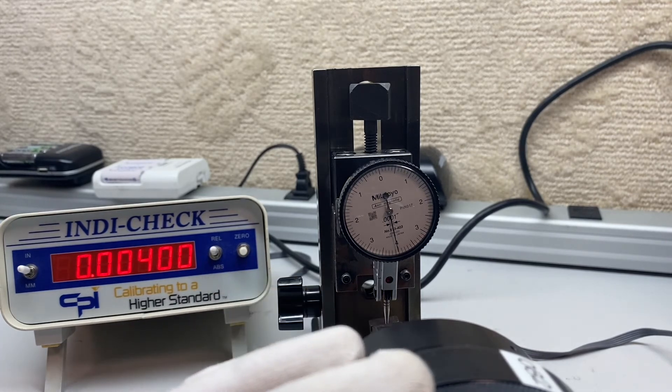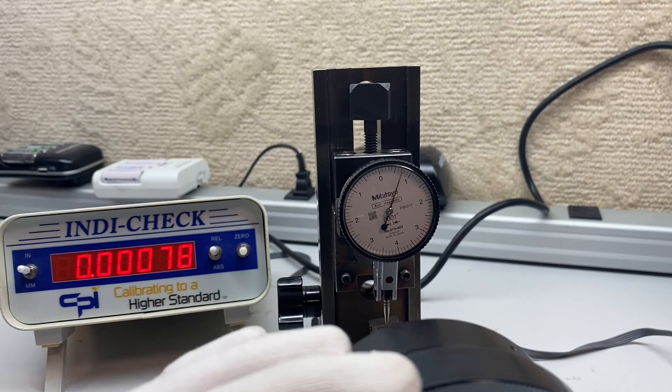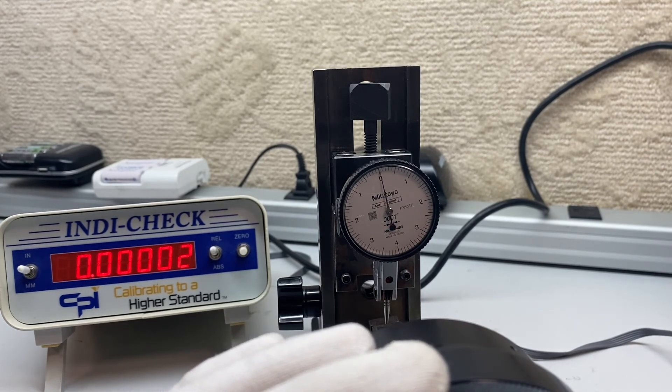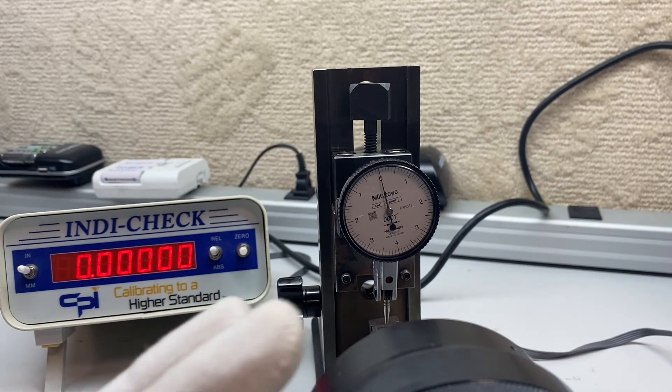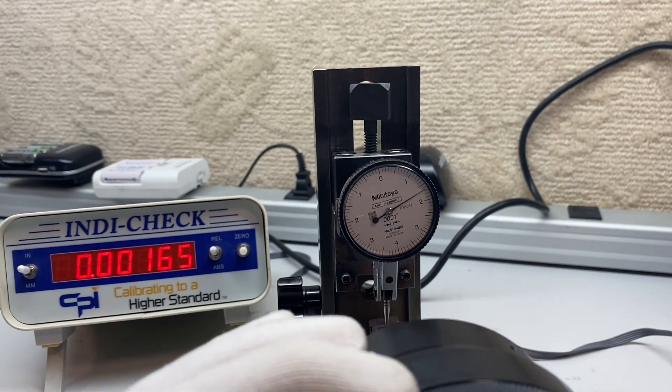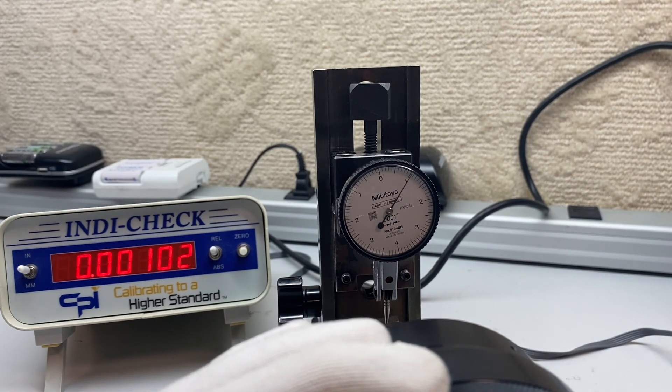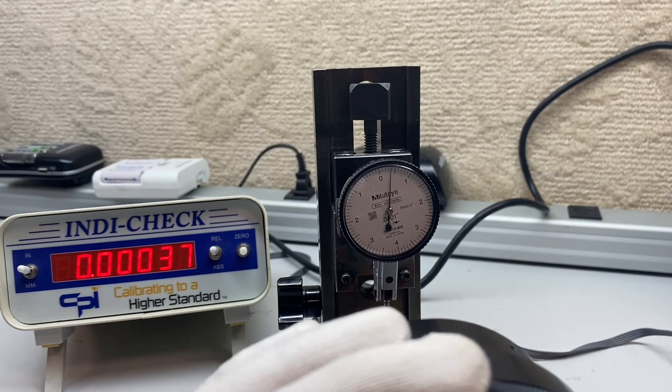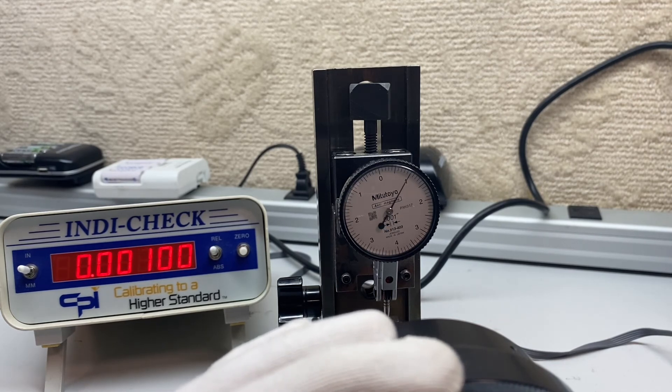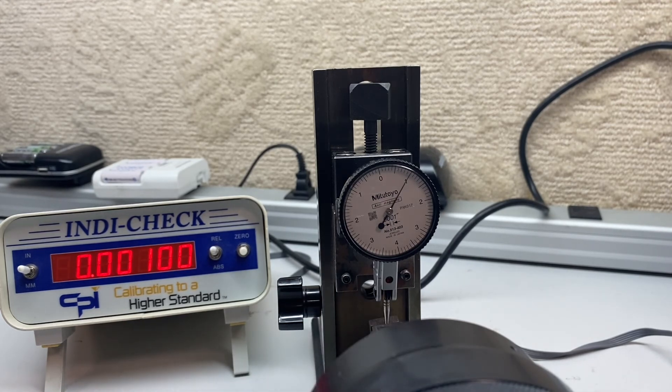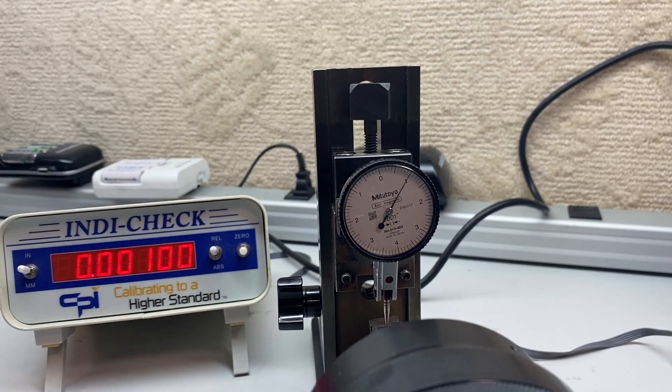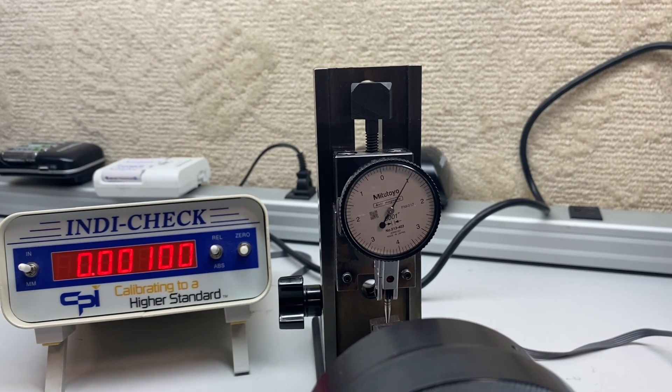And then we'll come back and check our zero. And zero. Still zero. We can come up and check hysteresis. It's back to one. We can come past it and come back here as well. Repeatability. Come up on it. Take a reading. It's looking good. So in the other video, we did the back calibration. In this video, we're doing the forward calibration. So that concludes the calibration of this test indicator. Thank you.